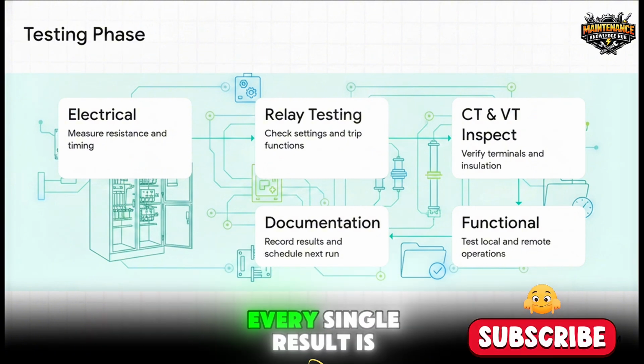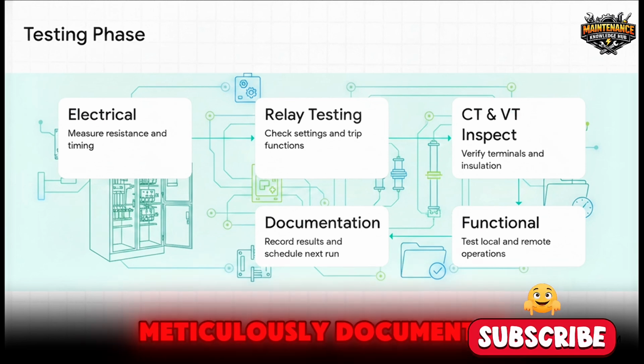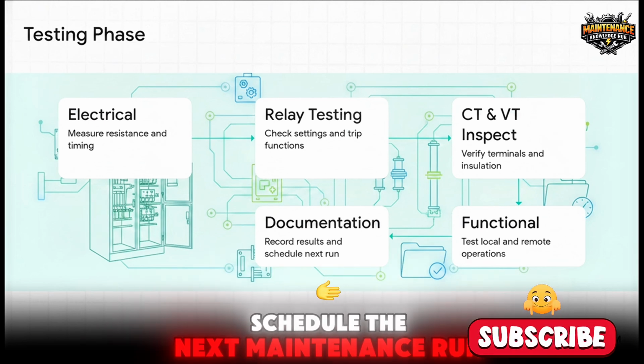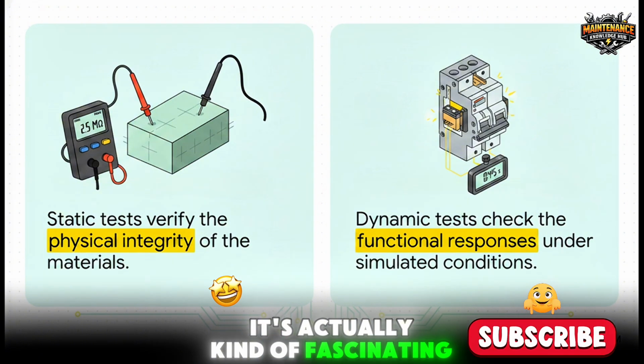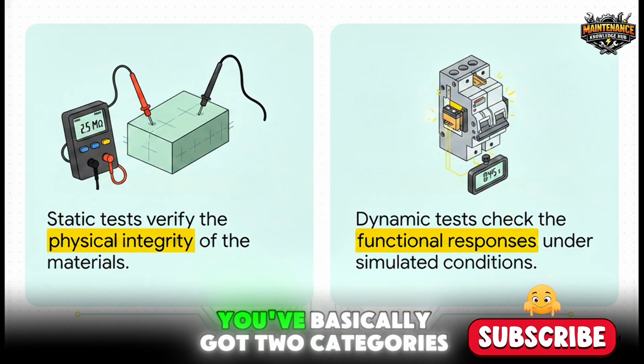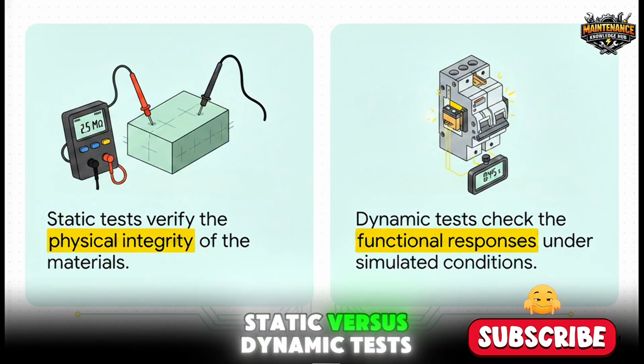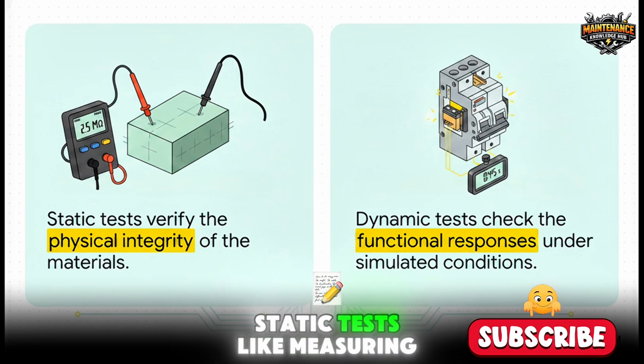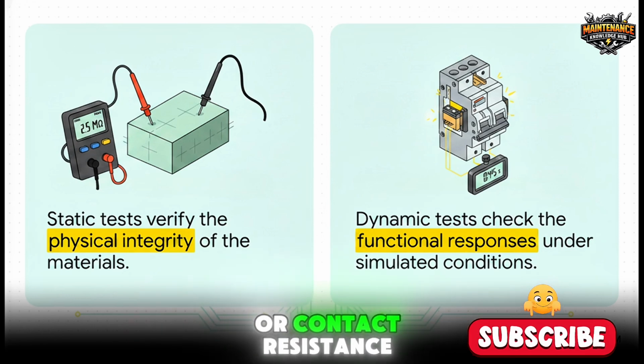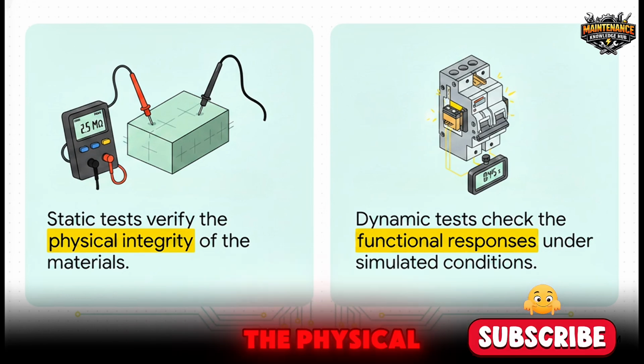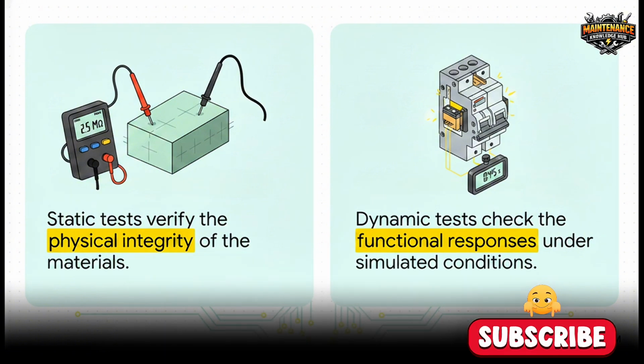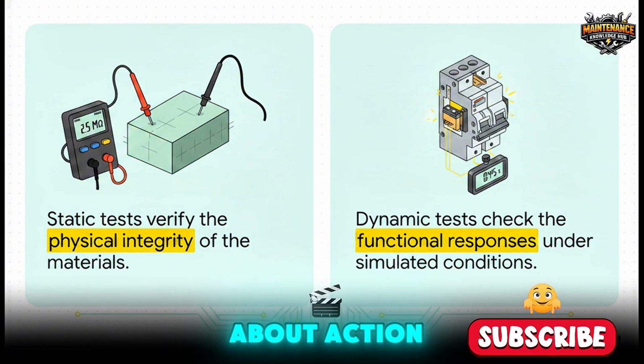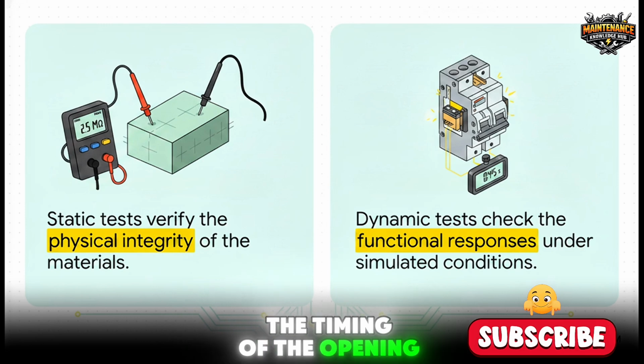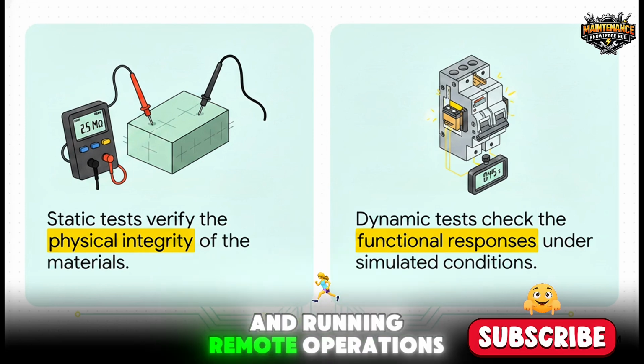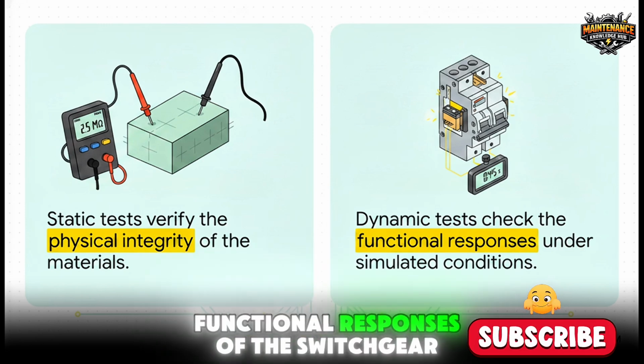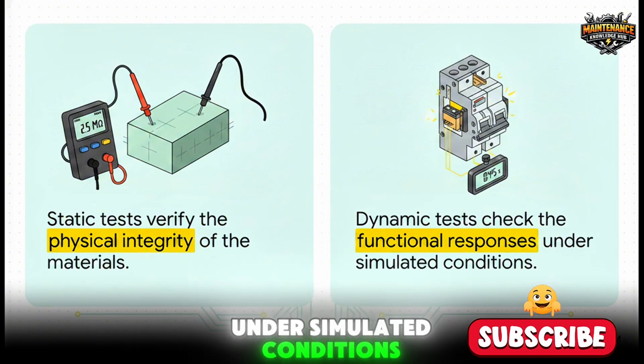And of course, every single result is meticulously documented so they can perfectly schedule the next maintenance run. It's actually kind of fascinating how they split this testing up. You've basically got two categories, static versus dynamic tests. Static tests, like measuring insulation resistance or contact resistance, are all about verifying the physical integrity of the materials themselves. Dynamic tests, on the other hand, are all about action. That involves testing the timing of the opening and closing, hitting the trip circuits, and running remote operations to see the active functional responses of the switchgear under simulated conditions.